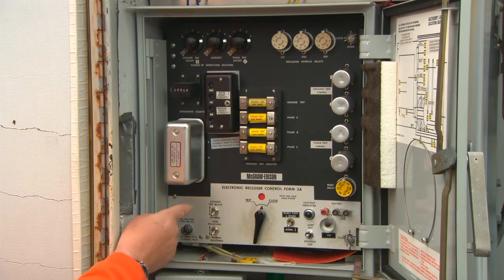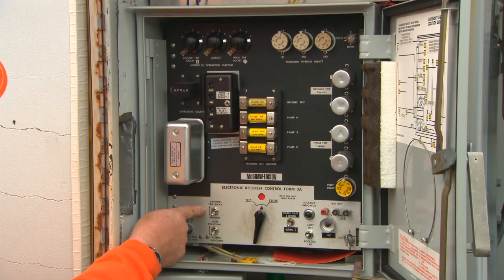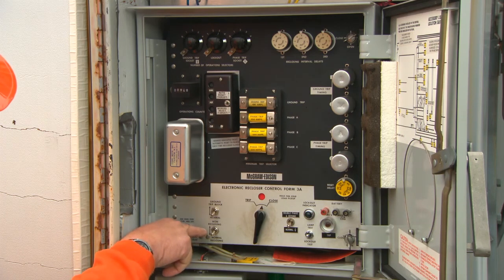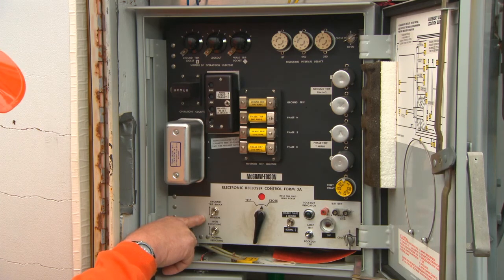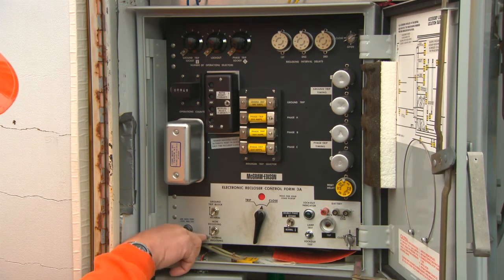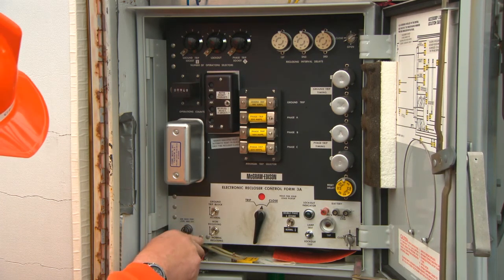On the bottom is a silver toggle switch for the ground trip blocked function. This is used for testing or switching requirements. Below that switch is another silver toggle switch for the non-reclosing function. This would be your hold-off switch. By switching this up to the non-reclose position, you will have a hotline tag. Switching it back down will enable normal reclosing.